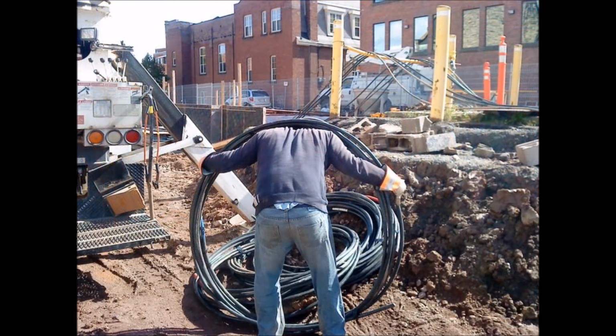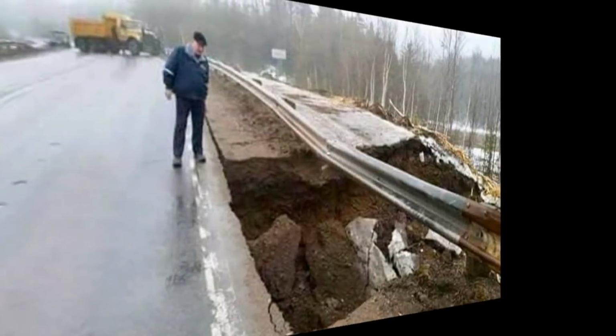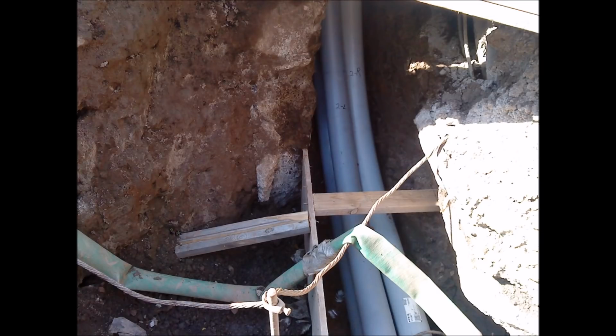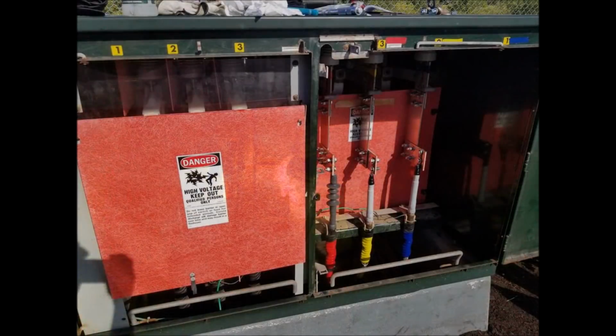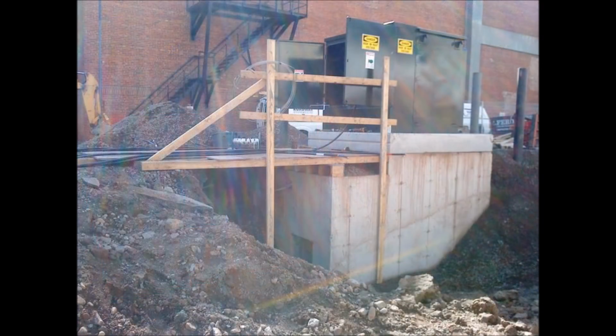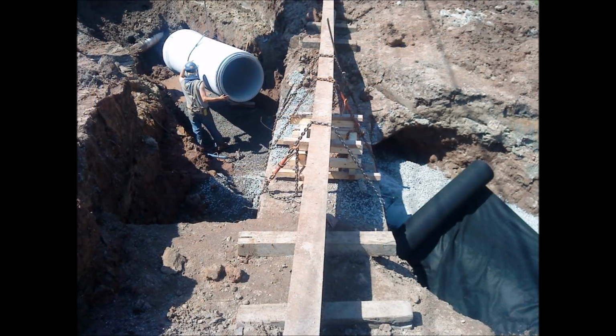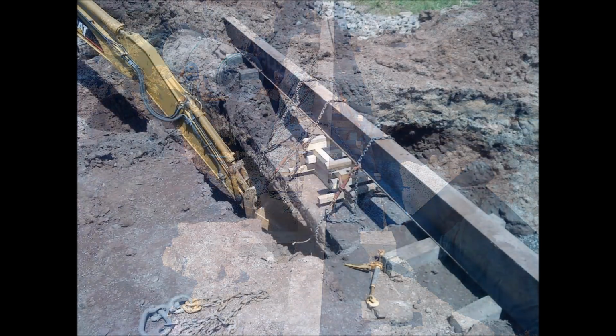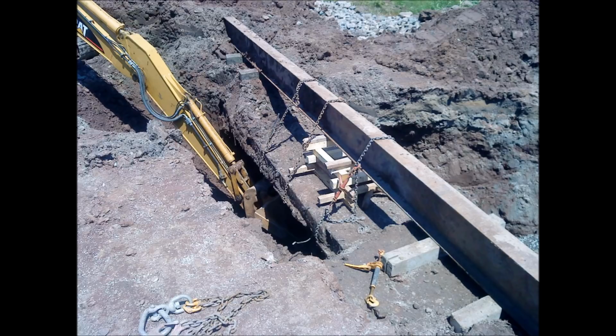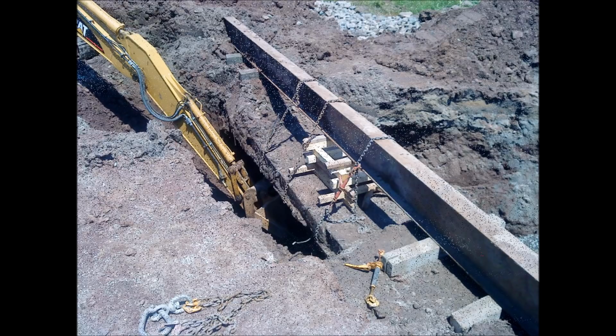Underground cables are also extremely heavy and awkward to work with compared to overhead lines. There is also flooding. Ductwork and high-voltage switching vaults make for the perfect transit system when water has nowhere to go, at which point we may have to de-energize an entire system for safety reasons. Underground lines also pose a hazard to construction crews and local city workers. Here, you see a local contractor using a steel I-beam to help suspend a concrete duct bank containing 7,200 volt cables as they dig below it.